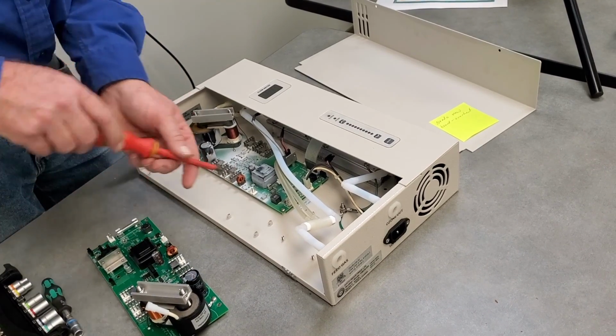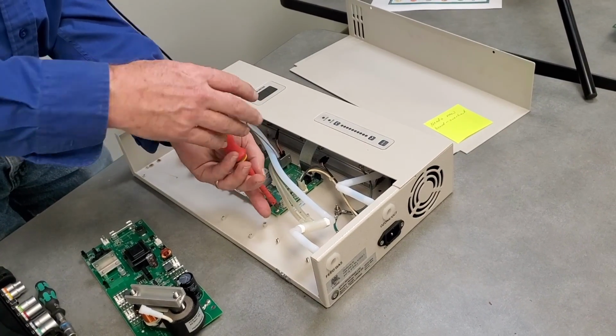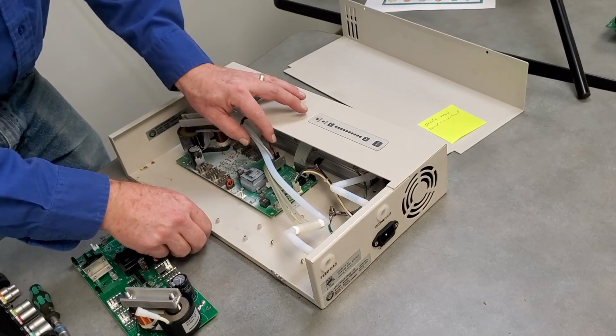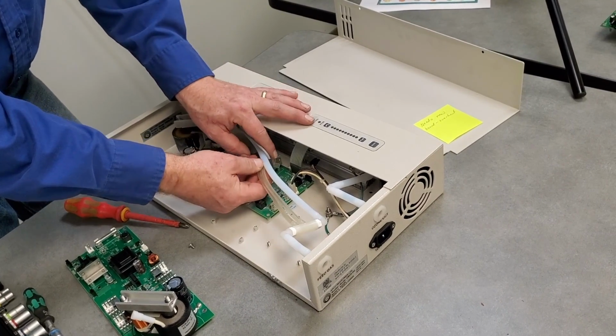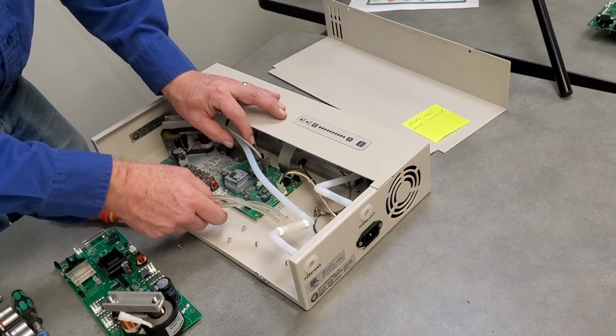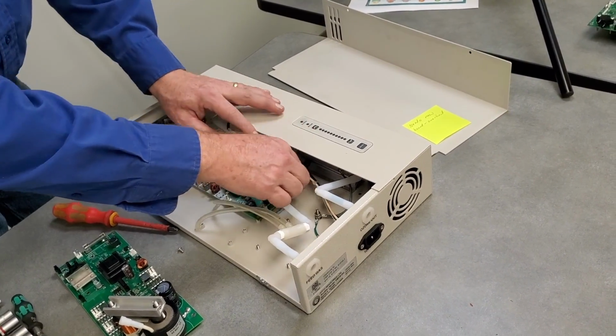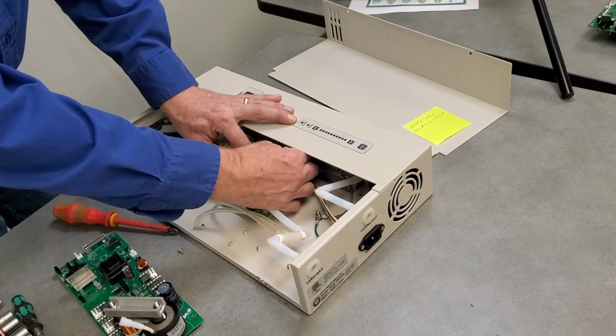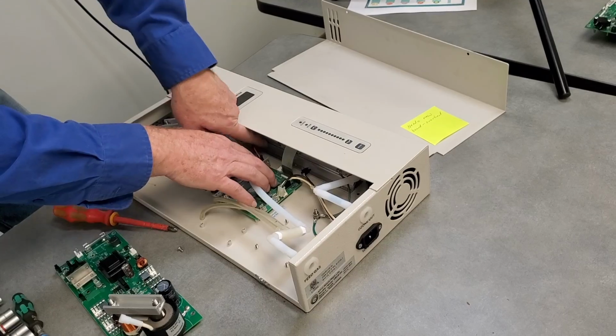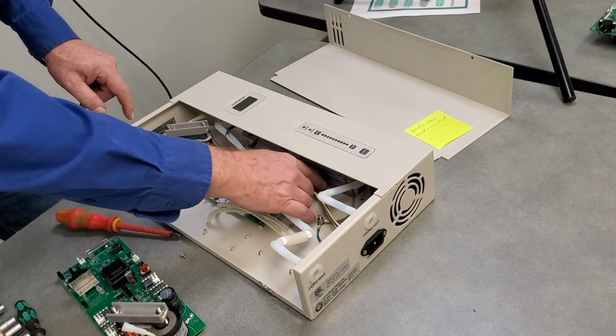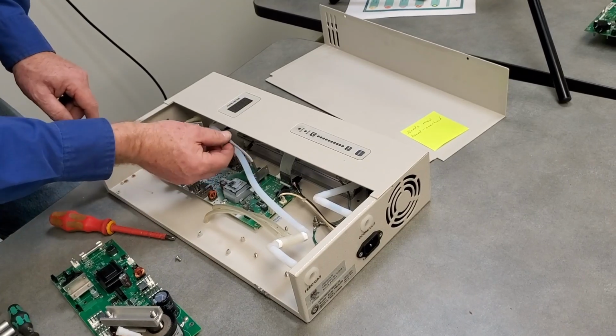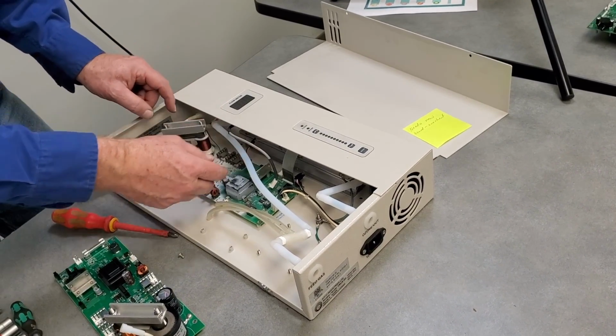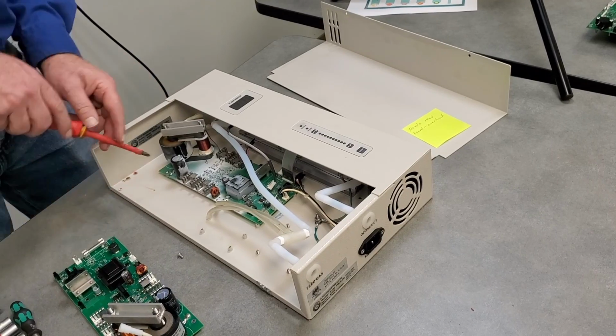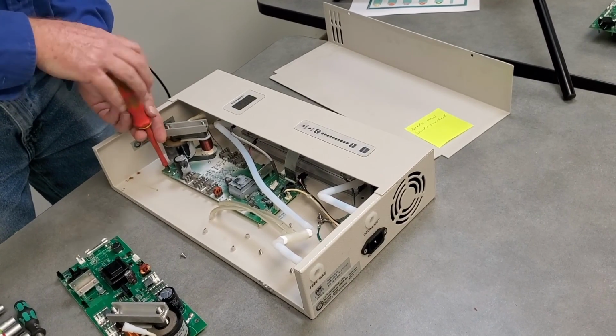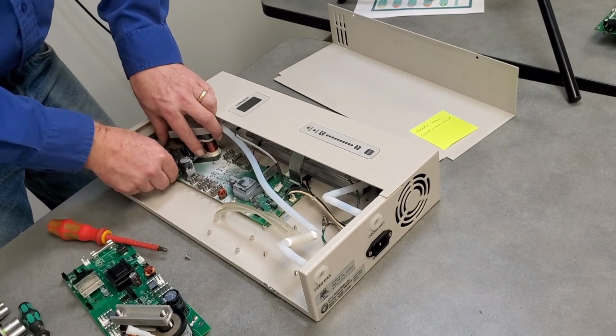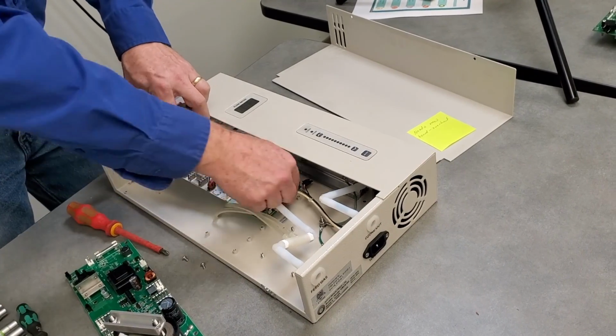So we've got one screw here left. There's these tubes here hook up to the flow sensor, so those need to be removed. Unplug the power. Unplug this ribbon cable, and there's a heat sensor to replace or to remove. Fan plugs in, and this is for your flow meter. Once those are replaced, and you take the screws out, you can replace the generator board.